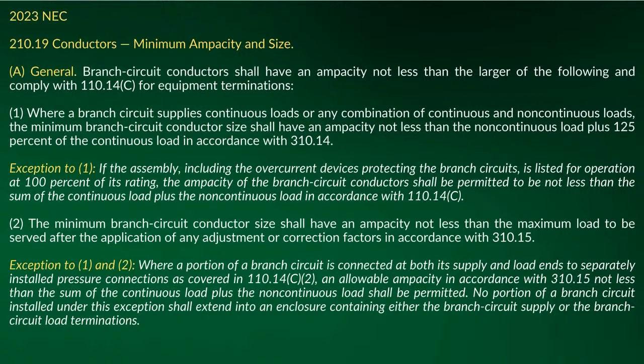And that's where all these changes took place, because there was misapplication of how to apply the percentages. So like you were saying in the opening statement, if everything's non-continuous, you can take it right up to 100% for 20 amps. But when you get into continuous loads, once you put the 125% on, that's the same as the 80% of the breaker. Now, you can have a breaker that is rated at 100% duty and take continuous loads all the way up to 20 amps if it's rated as such.